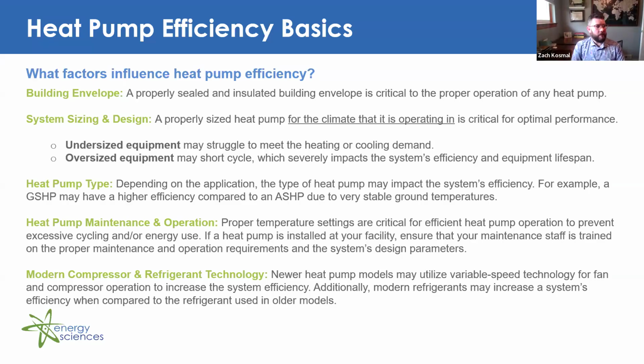Next, we have heat pump maintenance and operation. Proper temperature settings are very critical for efficient heat pump operation to prevent excessive cycling and energy use. If the heat pump is installed at your facility, ensure your maintenance staff is trained on the proper maintenance and operation requirements, and also the system's design parameters. Some examples of proper operation and maintenance may include correct thermostat settings based on that system's design for heating and cooling, coil and filter cleaning, regularly checking your refrigerant charge, and ensuring proper airflow.